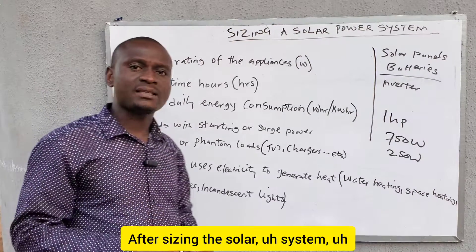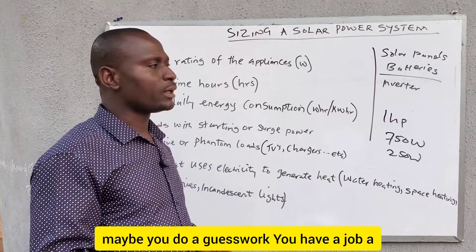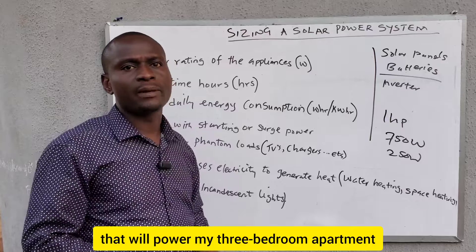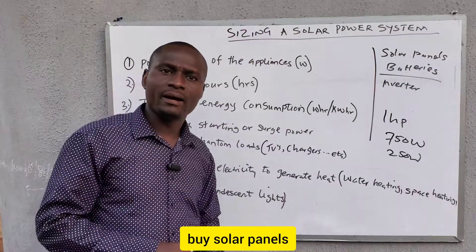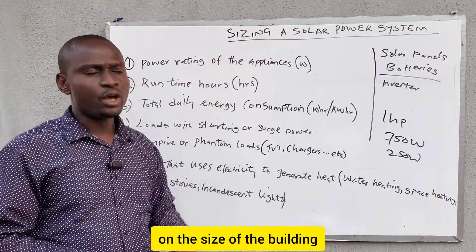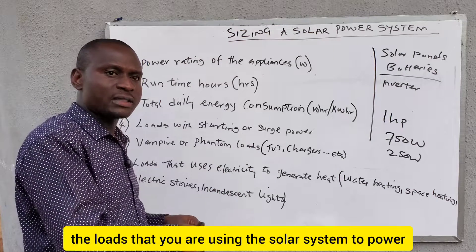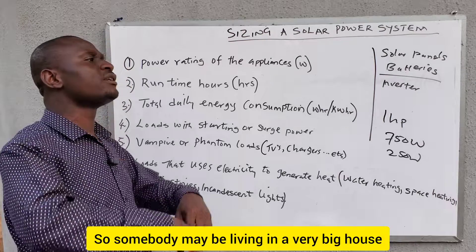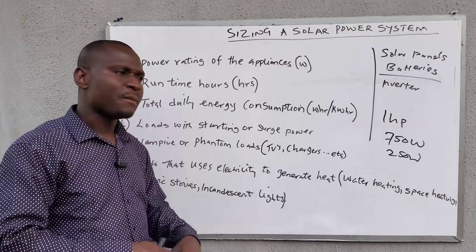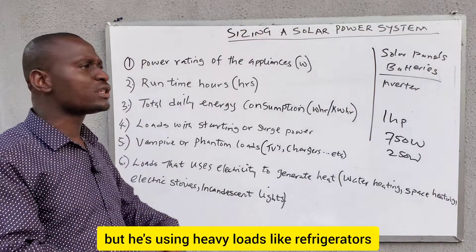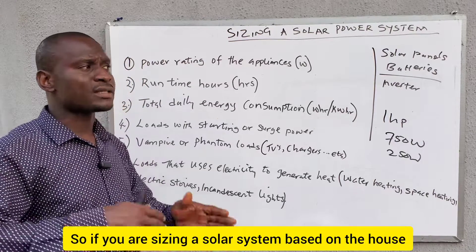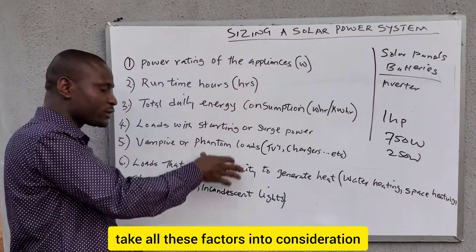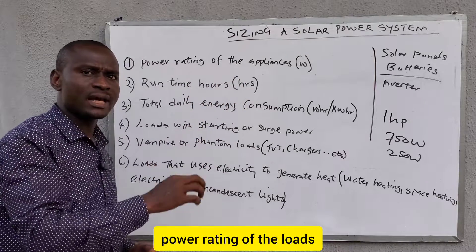When you don't take these things into consideration and you do a guesswork — for example, a client calls and says they live in a three-bedroom apartment and need solar — you must not just rush to the market and buy an inverter, batteries, and solar panels. You do not size a solar power system based on the size of the building. You size it based on the loads you are using the solar system to power. It is the loads that determine the size of the system, not the building. Somebody may live in a big house but only need a few appliances, while someone in a small apartment may use heavy loads like refrigerators and water pumps. So check and take all these factors into consideration.